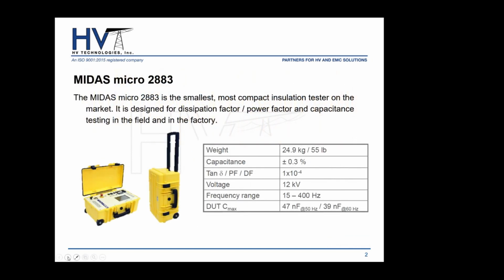All right, so the MIDAS Micro 2883 is right now the smallest, most compact insulation tester on the market. It is designed for dissipation factor or power factor, as it is also known, and capacitance testing in the field and in the factory. So with this instrument, it includes all the features needed to perform tests on various high voltage components. It has a 12 kV voltage source that delivers a clean signal, a variable frequency source for advanced measurements or bushing analysis, for example. It has an internal gas-filled standard capacitor, which guarantees repeatable results and long-term stability.